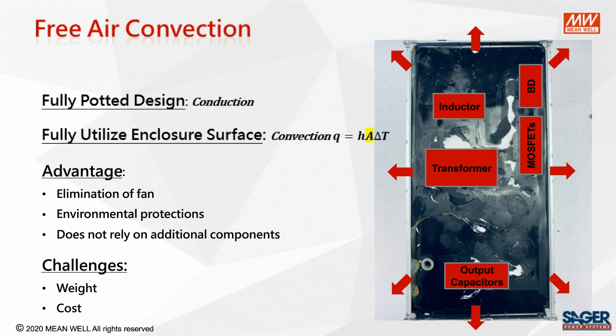This is another reason why free air convection power supplies are limited to medium power applications, in addition to the heat removal effectiveness. Another challenge is cost. Since the heat removal effectiveness is lower compared to other fanless and fan cooled designs, we have to use higher grade components that provide higher efficiency. So a big challenge in designing practical free air convection type power supplies is also considering the cost effectiveness of the various components. And the potting compound is not cheap either.